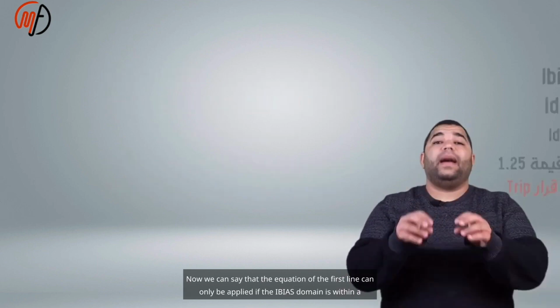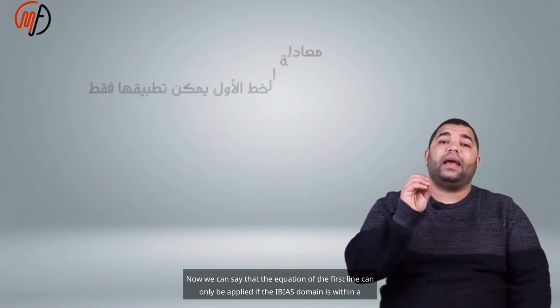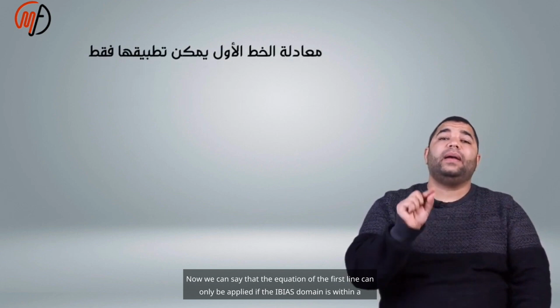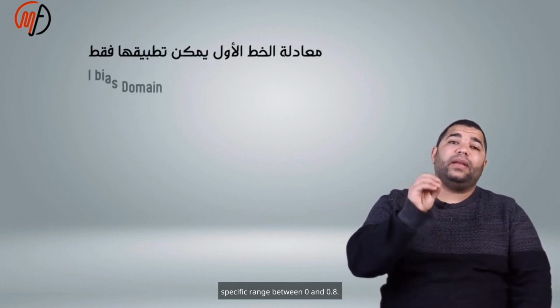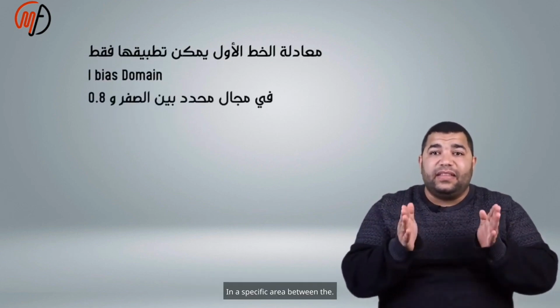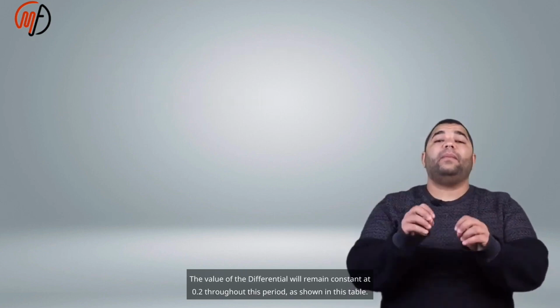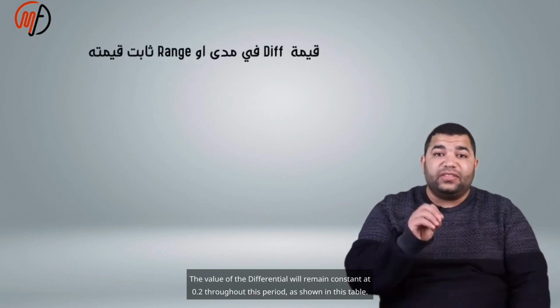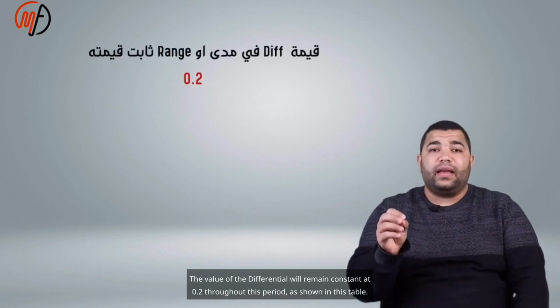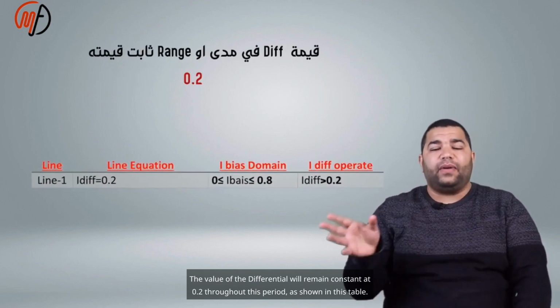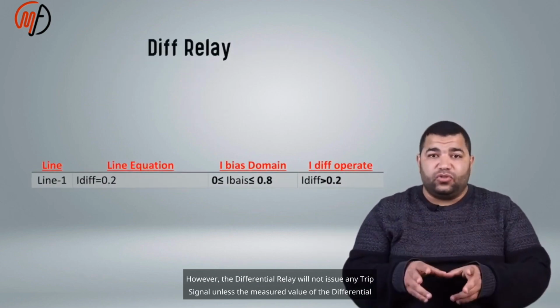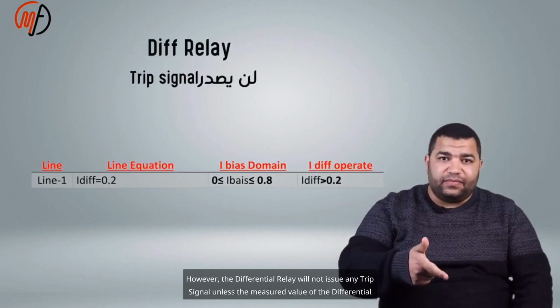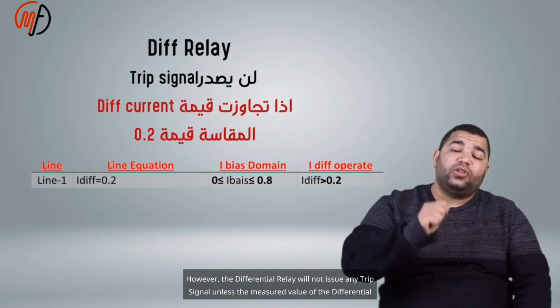Now we can say that the equation of the first line can only be applied if the I bias domain is within a specific range between 0 and 0.8. In this range, the value of the differential current will remain constant at 0.2, as shown in this table.